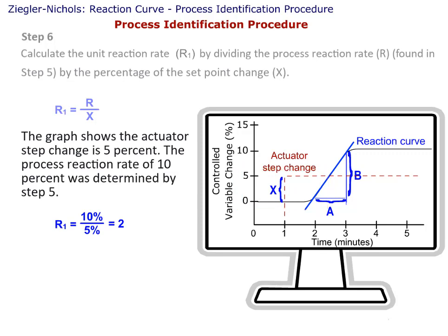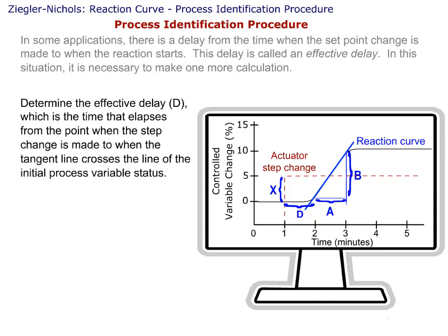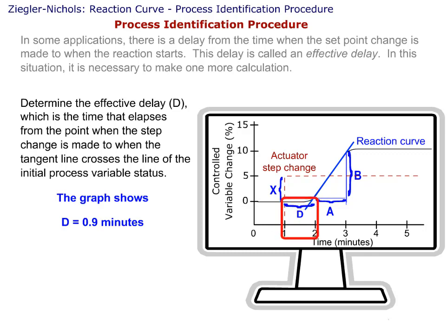The process reaction rate of 10 percent was determined by Step 5. In some applications, there is a delay from the time when the set point change is made to when the reaction starts. This delay is called an effective delay. In this situation, it is necessary to make one more calculation. Step 7: Determine the effective delay, or D, which is the time that elapses from the point when the step change is made to when the tangent line crosses the line of the initial process variable status. The graph shows D equals 0.9 minutes.